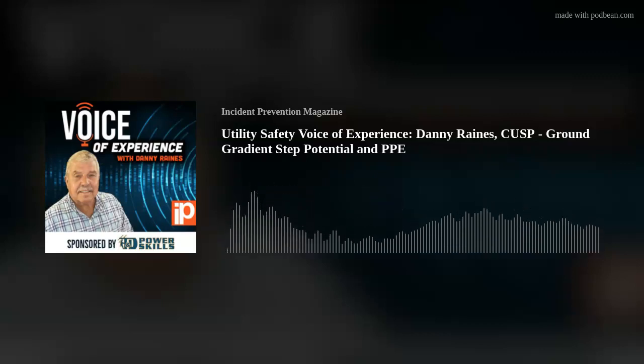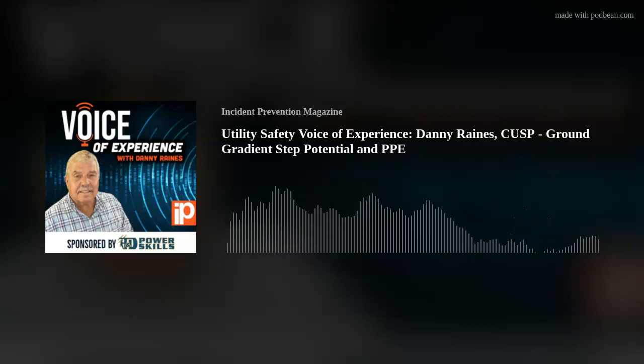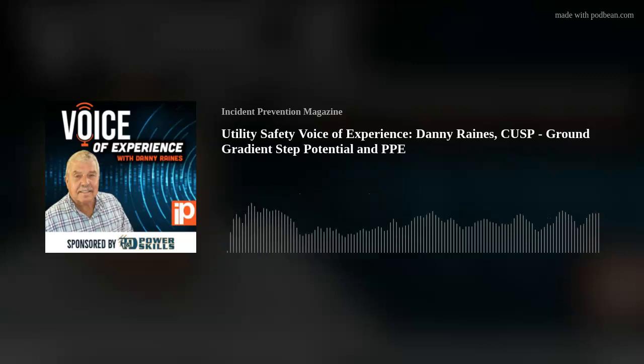Rule of thumb, our practice where I worked for 40 years: if it was a live front transformer, we knew it, and we'd stay behind the door. We'd remove the lock, take the captive bolt out, and then open the door, staying behind the door the whole time, just in case there's something in there that we didn't want to affect us. That way we'd still have that metal door between us and it. So you have to be very, very careful. Remove those panels with a stick.